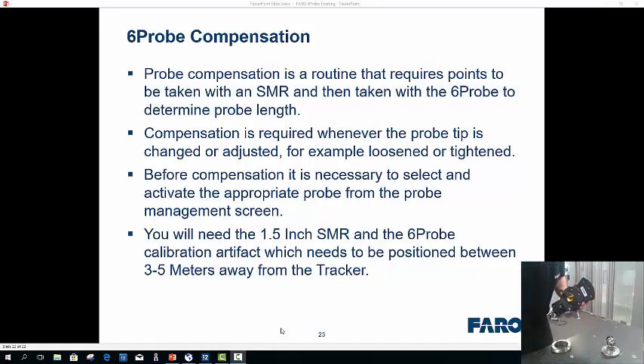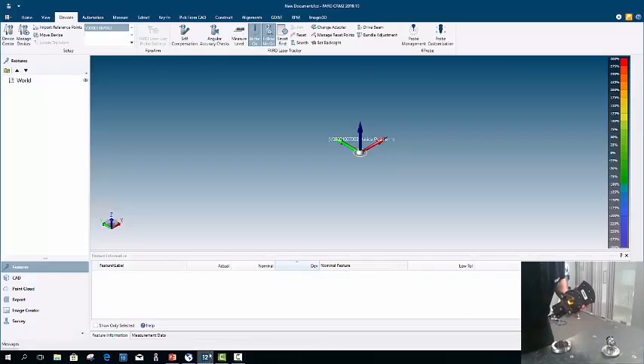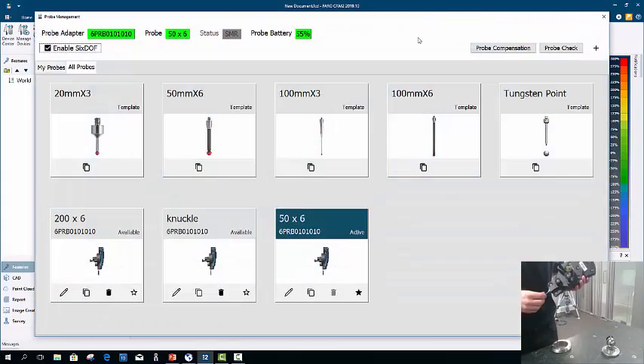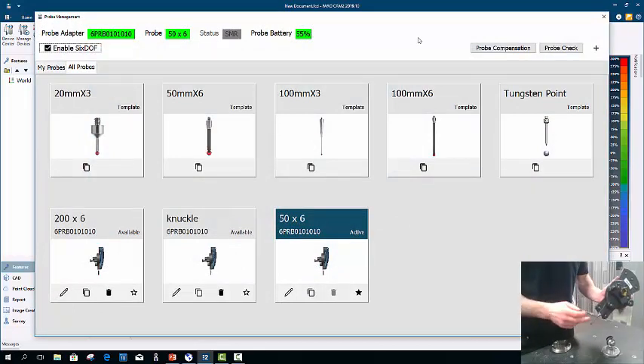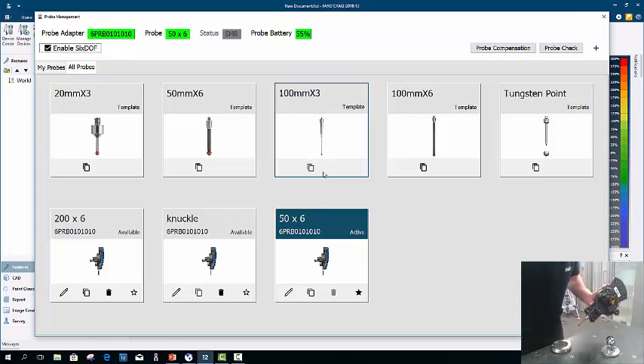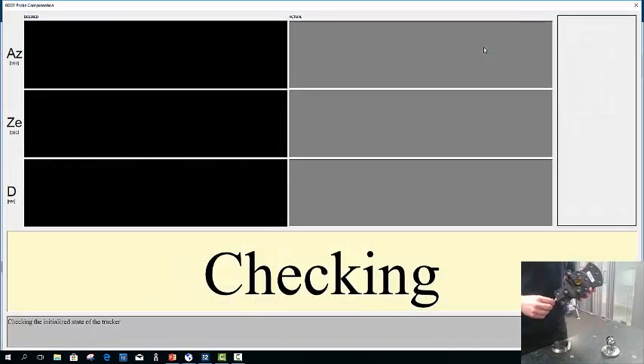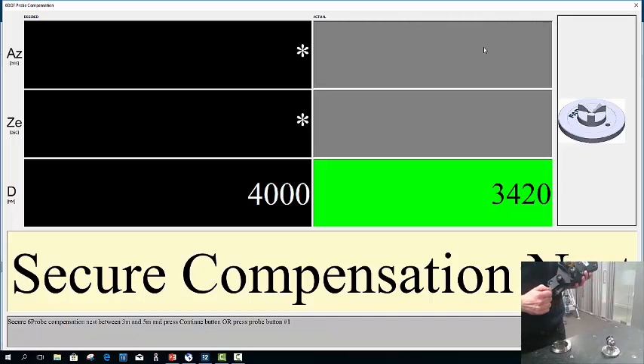To begin the probe compensation procedure, we open the probe management screen. We then need to select and activate the probe that we are using, in my case a 6x50mm probe. We click on it to activate it. Then we go to probe compensation in the top right hand corner of the probe management screen. The probe compensation screen will then open and give you a command as to what to do next.